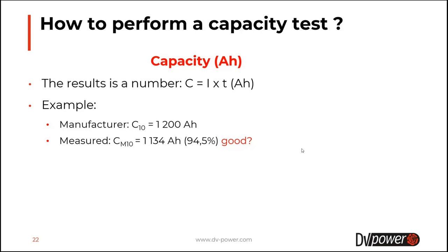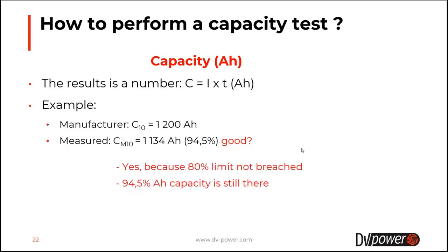Well, according to standards, the limit for battery capacity is 80%, and this battery is a good one because its capacity percentage is a lot higher than the 80% limit, and we can say that this battery does not need replacement. It can be put in service for one additional year, and we will test it again next year as standards require.